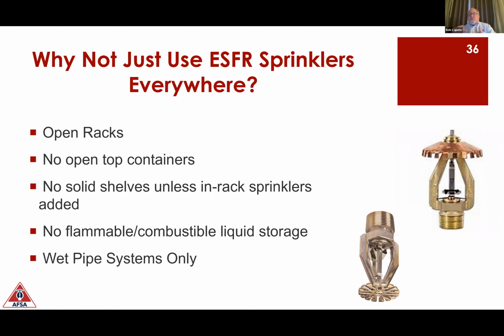So any combustible or flammable liquid will be lighter than water and float on top. These sprinklers put out about 100 gallons of water per minute. So voluminous amounts of water coming out of these sprinklers. And if I have flammable or combustible liquids, they're literally going to be on fire, floating on the water and spreading the fire in the path of least resistance for the water. Wherever the floor is not level, the water is going to carry the fire to other parts of the storage occupancy. So for that reason, I have all of these restrictions.